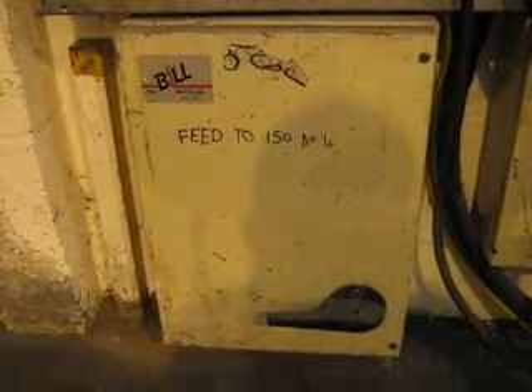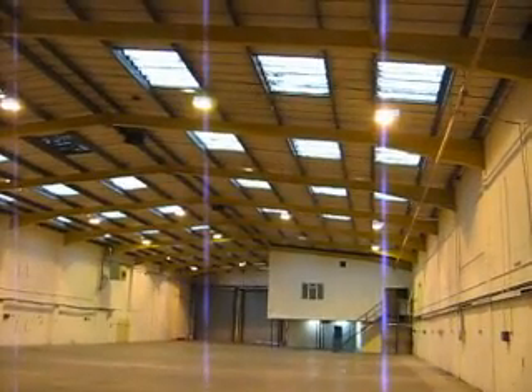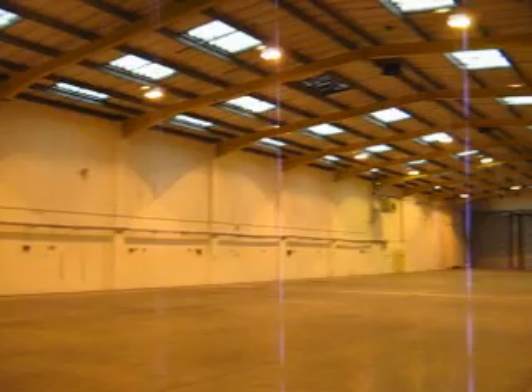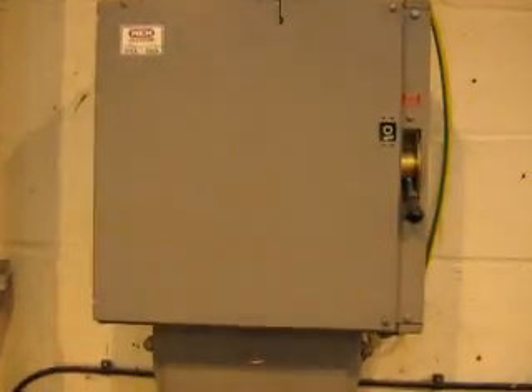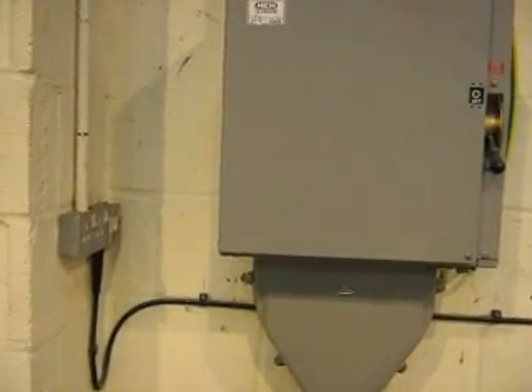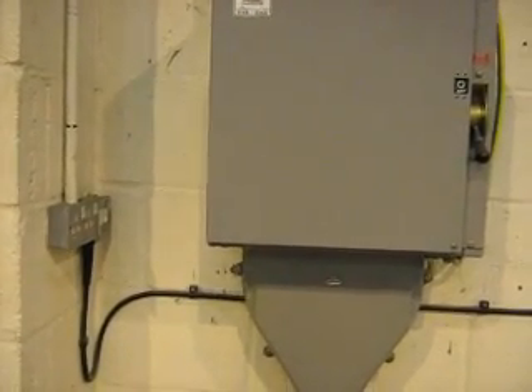These various disconnectors are marked up as feeding isolators, which are numbered. High bay, high pressure sodium vapor lamps, and around the side is a run of trunking that's quite damaged. This is a 15 amp fuse switch. It's switched off. We'll have a look inside in a moment. I don't know what its purpose is at the moment. I think it's feeding another fuse switch by the looks of it.